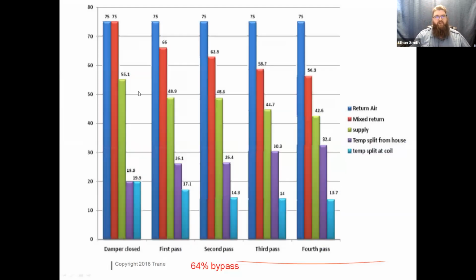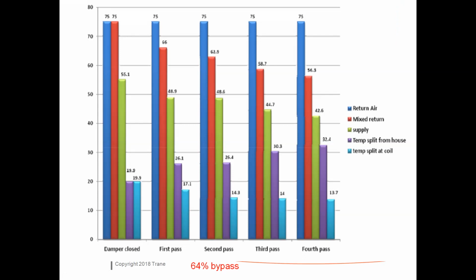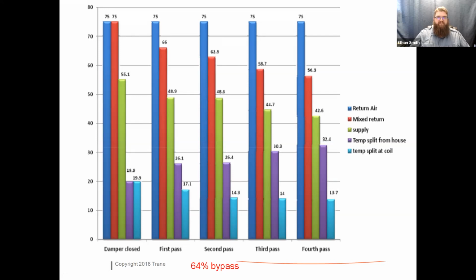Now, if we take that and close 2 zones on that system, we go to a 64% bypass. You can see what's happening to my numbers. It's just more dramatic. We're starting to get a discharge air temperature of 42 degrees. What do you think that coil temperature is if my discharge air is at 42? Mid-30s? I'd probably say high 20s. Okay, because I'm mid 30s over here.